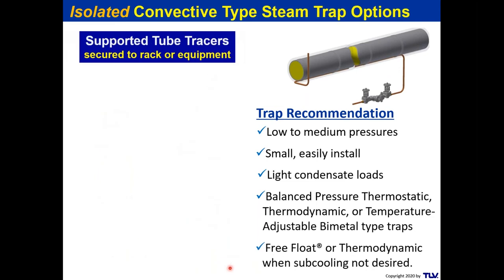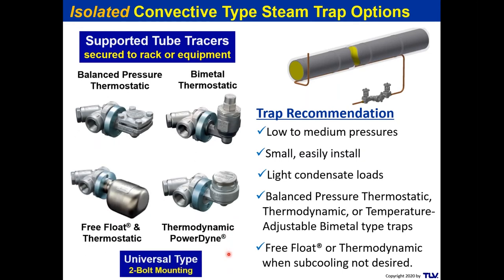For a supported convective tracer — mechanically secured — we still have similar pressure and condensate conditions but can use a heavier steam trap. A universal two-bolt mounting system works well here, using pipeline strainer connectors permanently installed in the piping so that a two-bolt steam trap can simply be bolted on and easily removed and replaced when maintenance is required.